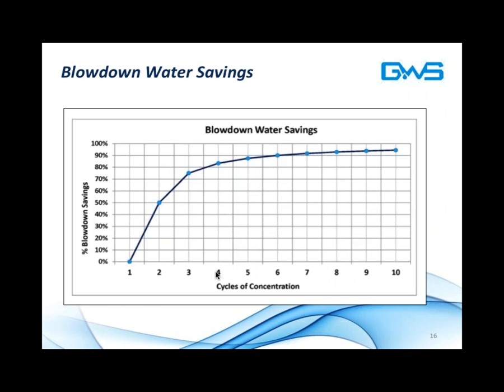Here's the graph that indicates blowdown water savings, and the same is true for makeup as well. The savings between 1 and 2 cycles is huge. It's tremendous. About 50% of your water is saved. When you move from 2 to 3, the savings diminishes, but it's still significant, 25% of water saved. And I mentioned a theoretical maximum of 9, 10, 11, or 12 cycles around there, when you have diminishing returns in terms of water savings. But in areas of the country where water is particularly hard, like in Southern California, for example, most cooling towers are running between 2 and 3 cycles. So anything that can be done to improve cycles of concentration will result in significant water savings. And of course, if you have a significant volume of water or a lot of cooling, even moving from 9 to 10 will yield significant savings when the volumes are large enough.